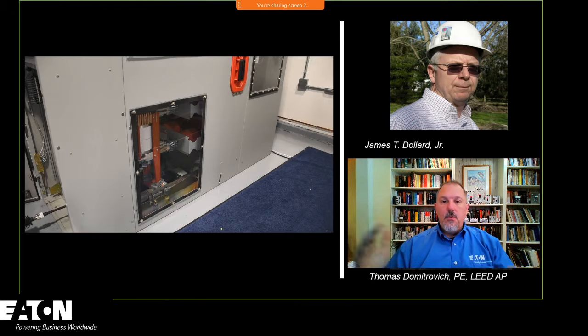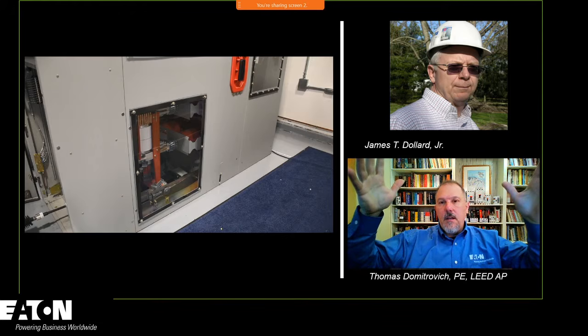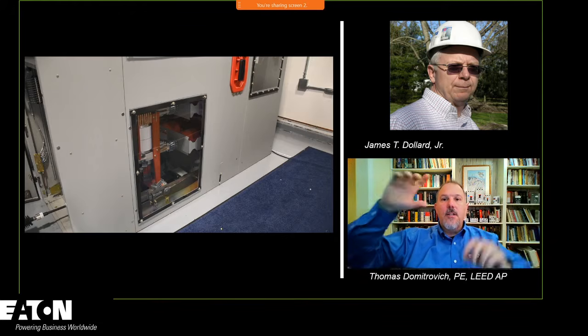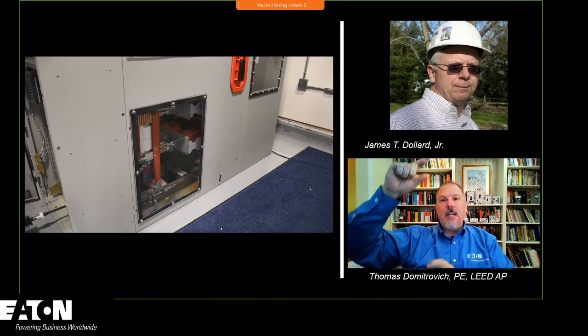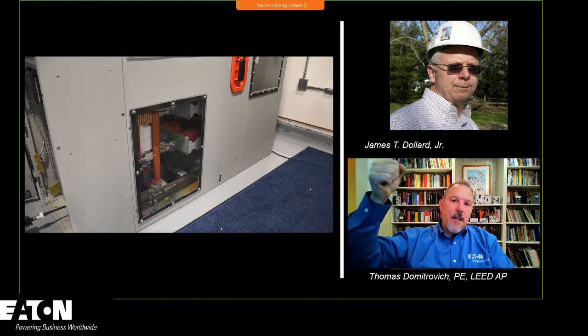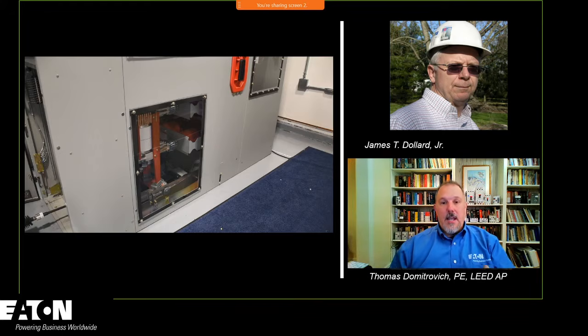We have the safety disconnect switch that has the disconnect on top of the equipment with a closed door. It's got a window so you can see the visible blades. We do presence of voltage indication. When you open that device, you can't open the door, but you can get to where you can access the fuses and replace them. So there's a lot of new technology, or maybe not even new technology, but more the ability and willingness to design things a little differently.